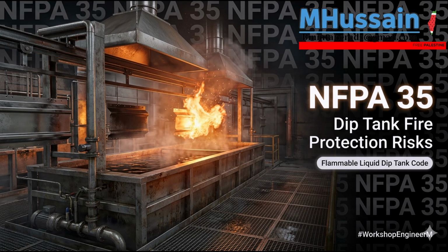If that operator unwraps that pallet in a Class 1 Division 1 area, where invisible, heavier-than-air explosive vapors are hovering around their ankles, that seemingly innocent, everyday act of tearing plastic wrap can effortlessly generate a spark capable of igniting the entire vapor cloud. That's terrifying. Therefore, the standard unequivocally forbids it. Pallets must be unwrapped in safe, unclassified receiving zones before the drums are moved onto the process floor. That is just wild, but it makes perfect scientific sense.